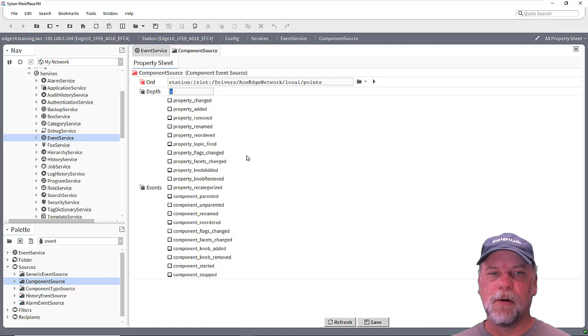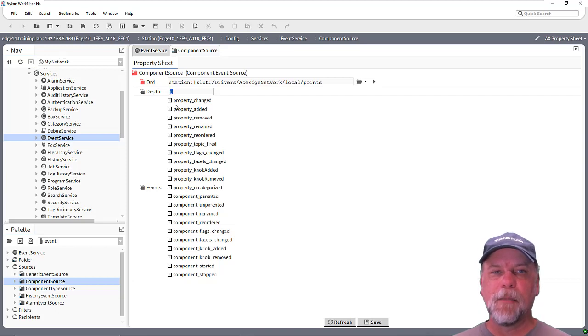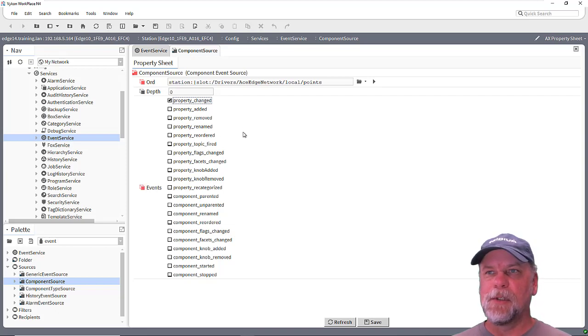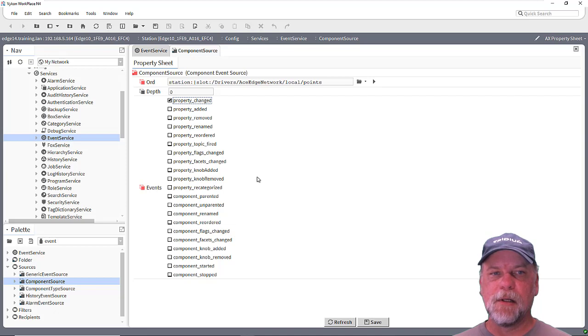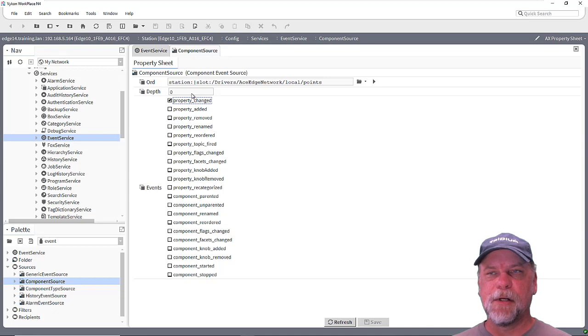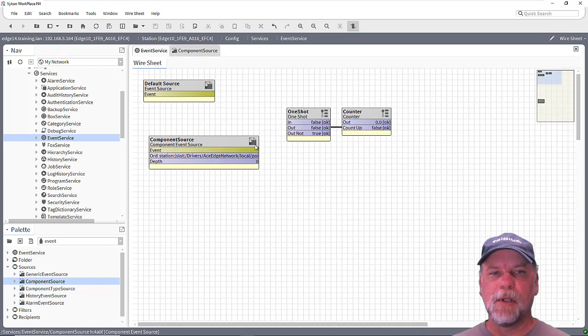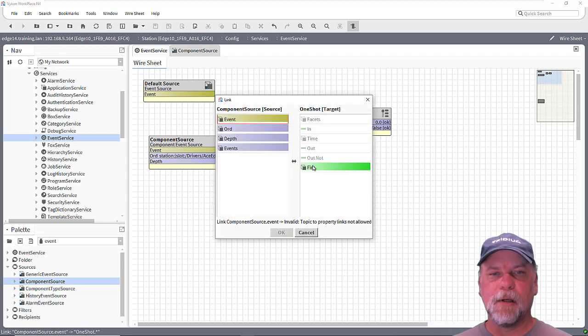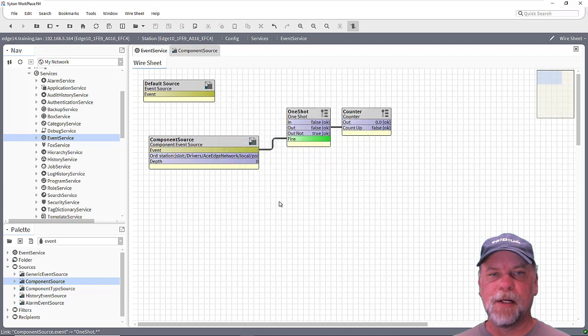Zero means just monitor the component that we're pointing to and look for any of these B component events that we want to monitor for — like a topic being fired, a link being added, the component being reordered, or renamed, or things of that nature. In this case, I'm just going to select the property changed flag on the component event to monitor. And I'll link the event topic to the fire action on the one shot here.